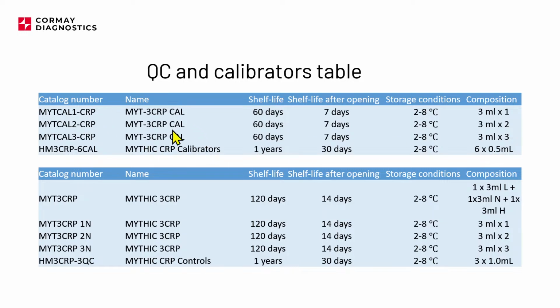And this is the hematology part. For the CRP part, we only have one calibrator, and actually there are 6 vials inside, because this CRP reaction is a spline type reaction. It's not linear, so we need to have at least 6 levels to make this calibration correct. During the calibration of the CRP reagent, you will need to run each level of the calibrator a minimum of 2 times. So actually the CRP calibration is time consuming, and later I will try to explain how often you will need to make this calibration.